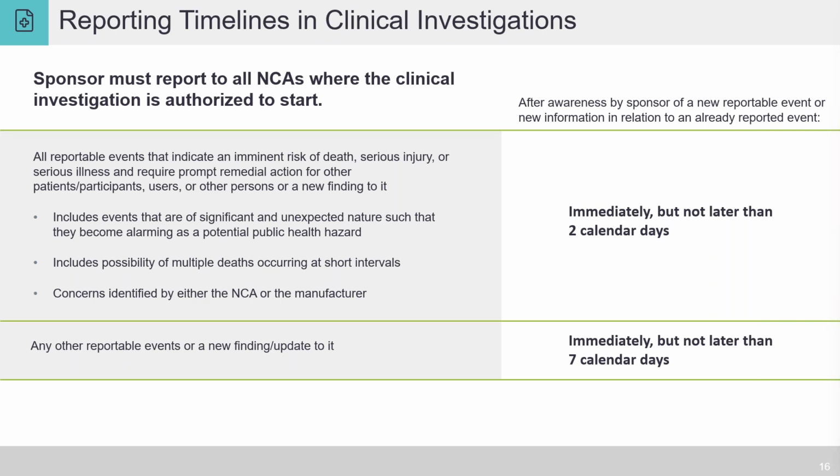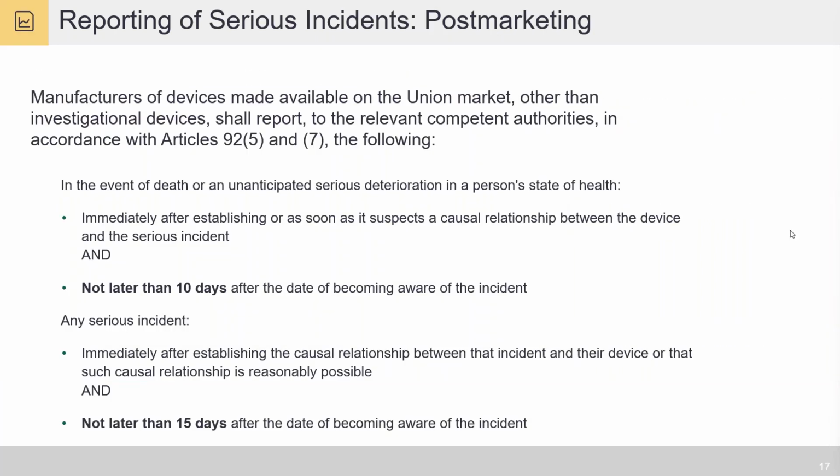Coming to the next slide, which is now reporting of the incident in the post-marketing scenario. So manufacturers of devices made available in the European Union market, other than investigational devices, shall report to the relevant competent authorities in accordance with the articles and the details specified in the MDR.